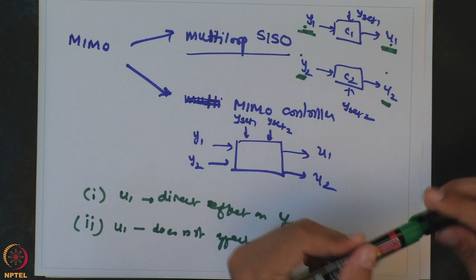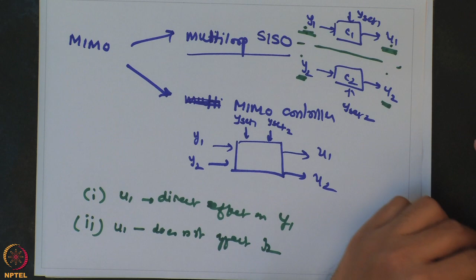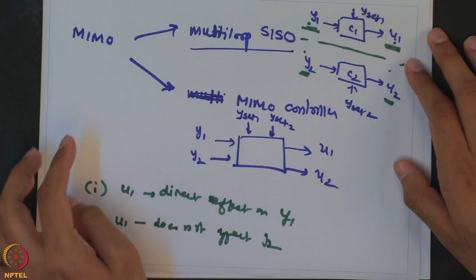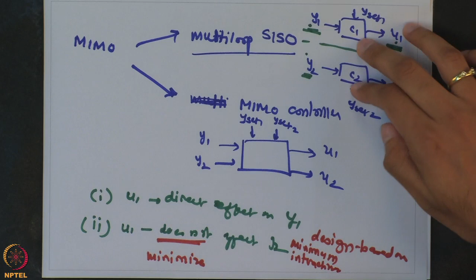Now, this is a very idealistic assumption, and if that was the case, then this strategy would work perfectly. But in reality, even as you can see from the previous example of inline blending, when you change U1, it not only affects Y1, but it also has an effect on Y2. So, when you find a variable which has a direct effect on Y1, you also want to minimize its effect on the other output. Rather than saying it does not affect, you will try to minimize the effect on other variables. That is known as design based on minimum interaction. So you want to minimize interactions between the two controllers. Ideally, when controller 1 is acting, it should not affect controller 2, but as long as U1 affects Y2, this controller will also get affected.